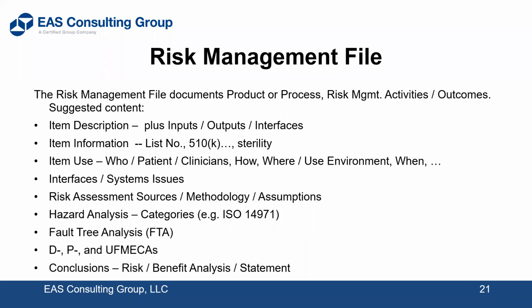So these are the kind of things I included in the narrative: a description of the product, how it's used, what interfaces are to the external environment, whether it's sterile, non-sterile, its 510(k) number, if it's a class 2 device, a PMA, etc. Who uses it? What is the environment in which it's used? Is it in a trauma unit? Is it OR, ER, at home use, whatever? Interface, connect to oxygen, connect to the plumbing system, electrical or battery, risk assessment sources, tools I used, or maybe my own company's CAPAs, maybe even some numbers referenced, NCMR numbers, assumptions. No matter how you go through this activity, you're going to find you are basing it on how far you drill down on assumptions tied to risk to the patient. And then the hazard analysis. And like I mentioned, I use a fault tree analysis, 3 FMEAs, and then I have the review under the conclusions.